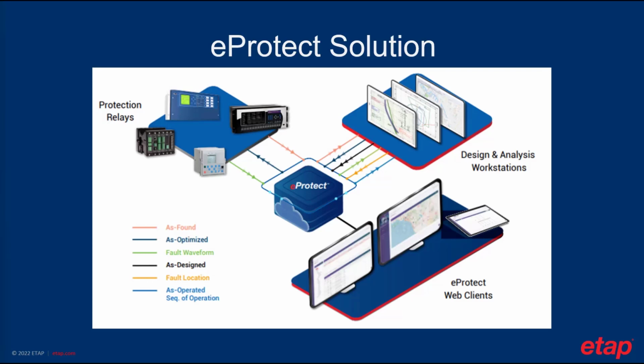So here we can download a COMTRADE file, do an analysis of that COMTRADE file, find the field sequence of operations and the as calculated sequence of operations in ETAP, and validate that your protection scheme actually is working the way it's expected to be. And then in the bottom right-hand corner we have the eProtect web clients, which gives you very good visualizations into all of the aspects of eProtect. And I'm going to go through all this in a demonstration.